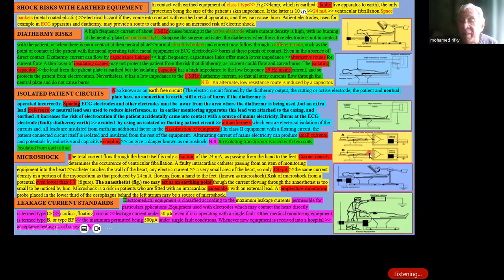Isolated patient circuit is a system nowadays using an isolating transformer. This isolating transformer, not like the normal transformer, is completely made of two circuits. The one circuit which has electricity is earthed, and the other one, the component of the monitor reaching the patient, is not earthed. It has coils, but the electricity in the primary coil is being transmitted to the other coil by electromagnetic forces. So there is no chance for the secondary coil to be affected by electric shock because it's not earthed. So this is what we call the isolating circuit.